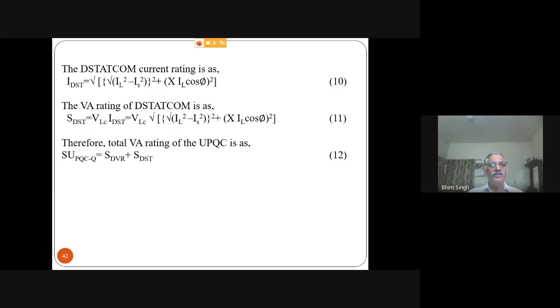As I told you, once you are able to make the current unity power factor by the shunt, the rating of your series compensator will reduce. Similarly, if you are able to provide some reactive power from the series, the rating of the shunt will reduce also. So all these aspects become very important.